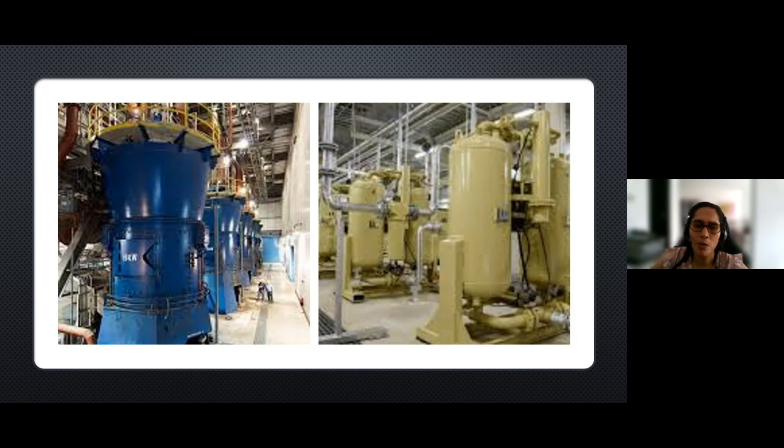An example I want to mention regarding this situation is that we realized in a coal power station that we had a continuous increase of the heat rate. We were monitoring mainly the boiler and the turbine, but we forgot a little bit about the auxiliary power consumption.